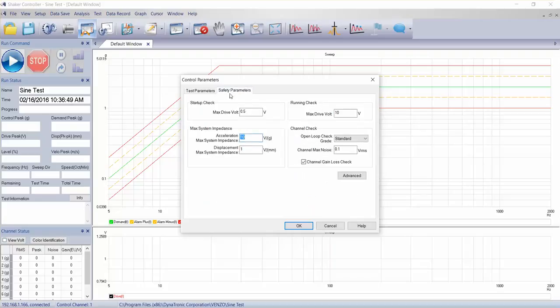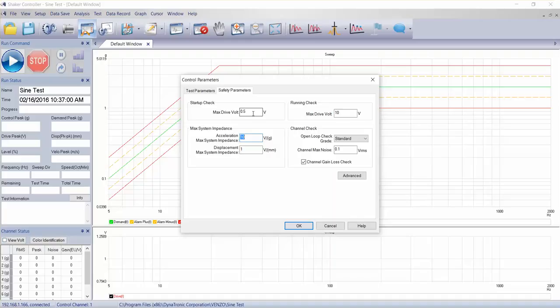We see a tab here for safety parameters. This is the startup check, this is a 0.5 volt as the default, and that's voltage out from the controller to the amplifier. Maximum of 10 volts output during running mode. That would be the full range output of the controller. Again, you could reduce that value if you wanted for safety sake.